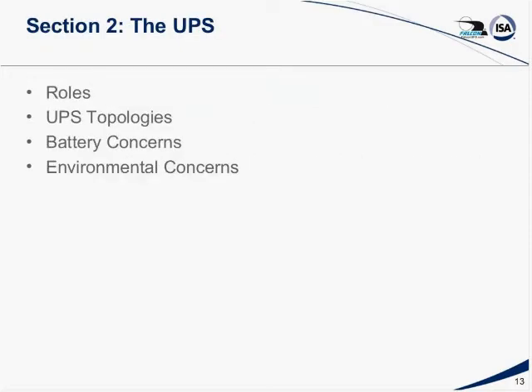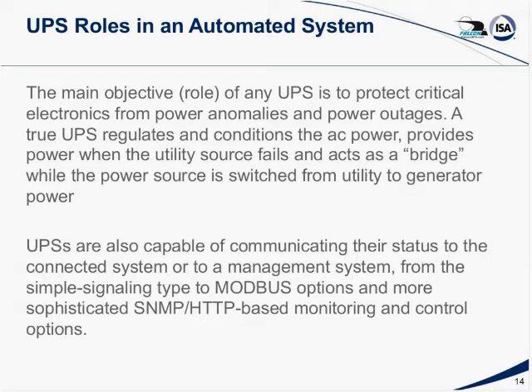All right, the next section we're going to talk about is the UPS itself. And we'll talk about the roles of the UPS, topologies, battery concerns, and environmental concerns. As we said before, the main objective of any UPS is to protect your critical electronics from power quality problems and from power outages. A true UPS will regulate and condition the AC power in addition to providing your transient and surge protection. It provides power when your utility source fails and acts as a bridge until you can get your auxiliary or alternative power sources running.